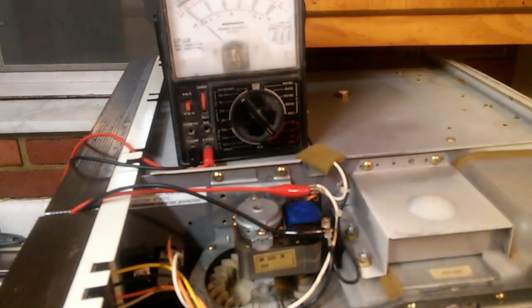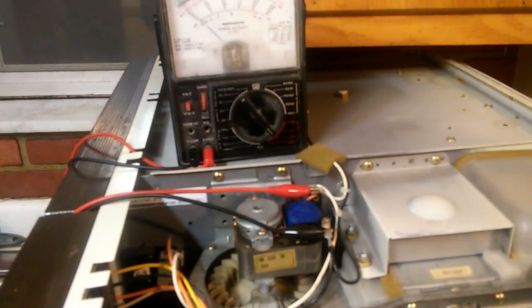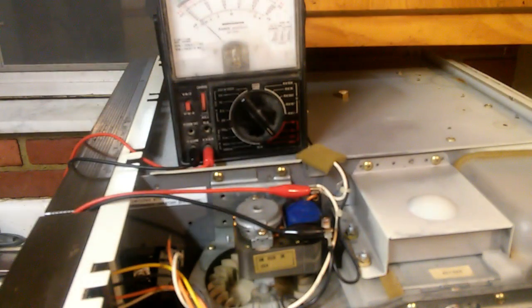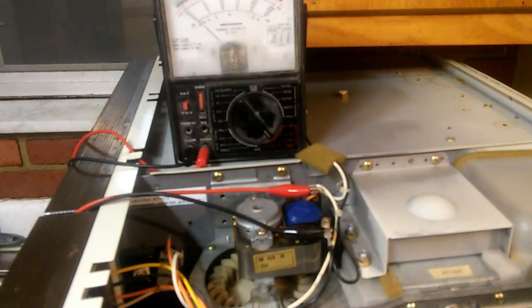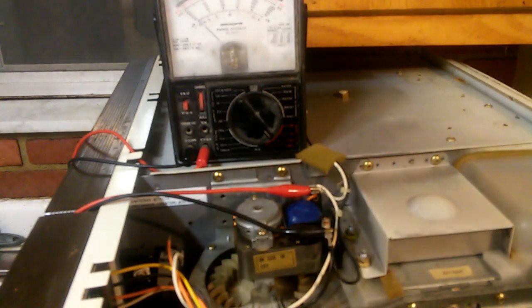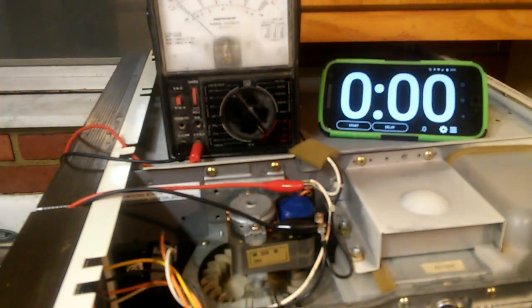Now, here's our fan. I've connected a voltmeter to the two lines coming into it, the white and black line, which should read 120 volts AC, just to make sure the fan is getting the correct voltage. The ambient room temperature right now is about 65 degrees Fahrenheit, a little on the chilly side, which is kind of what we want, since the problem seems worse when it's cool. I'll also put our stop clock here so we can see how long it actually takes.